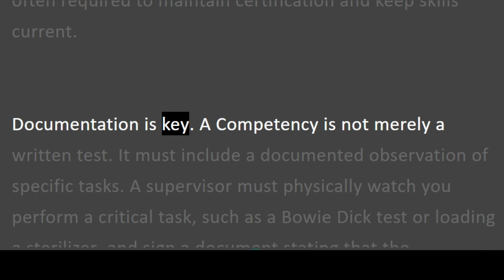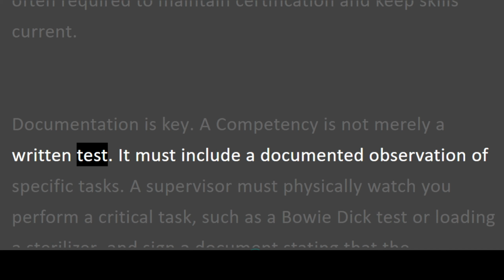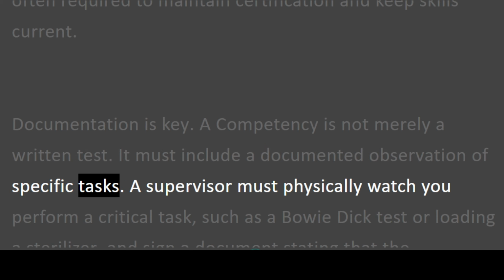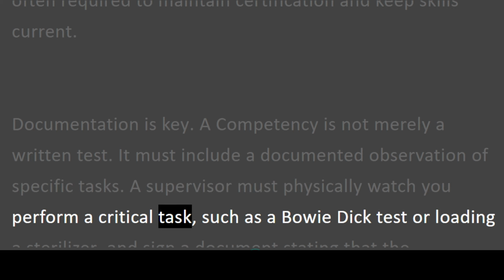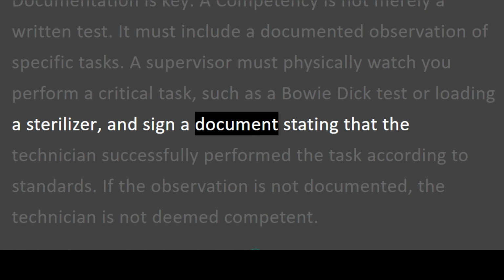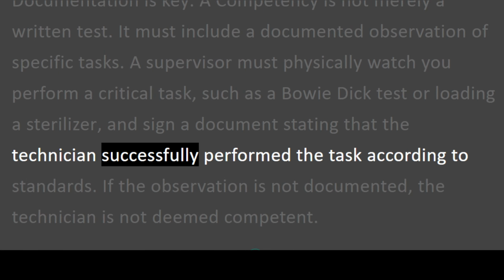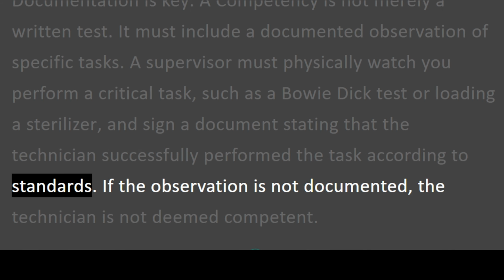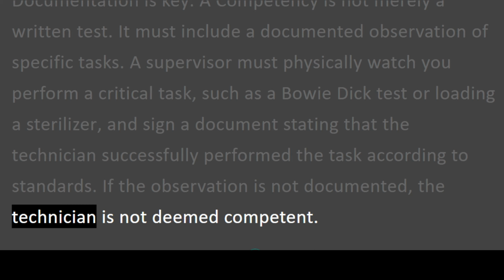Documentation is key. A competency is not merely a written test. It must include a documented observation of specific tasks. A supervisor must physically watch you perform a critical task, such as a Bowie-Dick test or loading a sterilizer, and sign a document stating that the technician successfully performed the task according to standards. If the observation is not documented, the technician is not deemed competent.